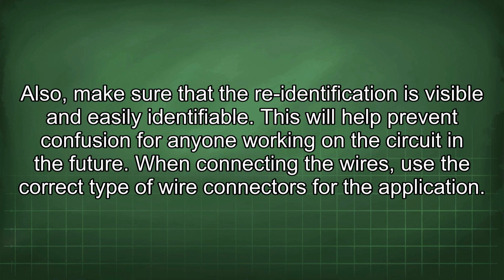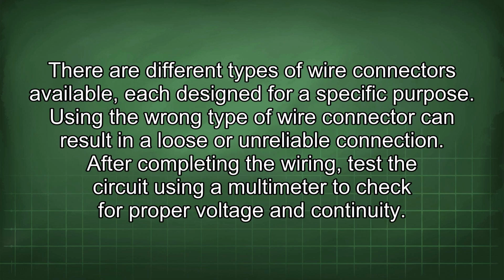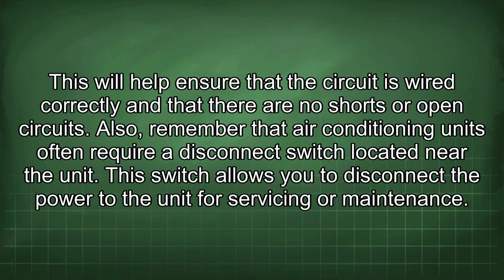When connecting the wires, use the correct type of wire connectors for the application. There are different types of wire connectors available, each designed for a specific purpose. Using the wrong type of wire connector can result in a loose or unreliable connection. After completing the wiring, test the circuit using a multimeter to check for proper voltage and continuity. This will help ensure that the circuit is wired correctly and that there are no shorts or open circuits. Also, remember that air conditioning units often require a disconnect switch located near the unit. This switch allows you to disconnect the power to the unit for servicing or maintenance.